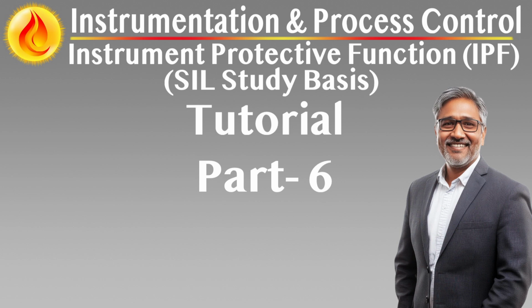Defined operating constraints. Depending on the risk, operations may be required to implement temporary limits, e.g., reduced feed rates, pressure thresholds, or flow caps until the IPF is re-enabled. Manual intervention readiness. Operators must be trained and prepared to take manual action, e.g., shutting a valve, stopping a pump, should the protected parameter approach critical levels while the IPF is out of service.